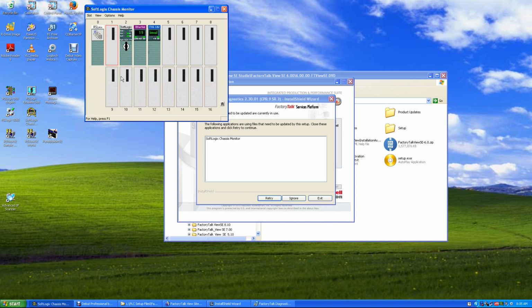And remember, we can have up to 6 processors. And this one RSLinx, just like Classic, this Enterprise will allow the HMI software to talk to all these processors. So clear out slot 1 and make sure that's empty. And then move your stuff over. Give yourself a blank slot 1. At the end of this, we're going to put RSLinx Enterprise in there.